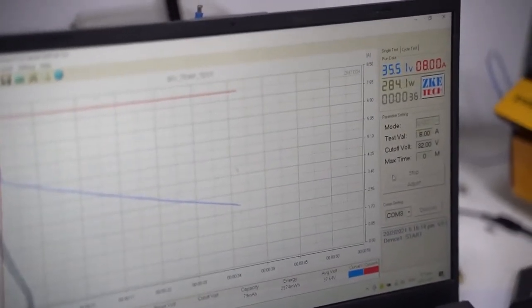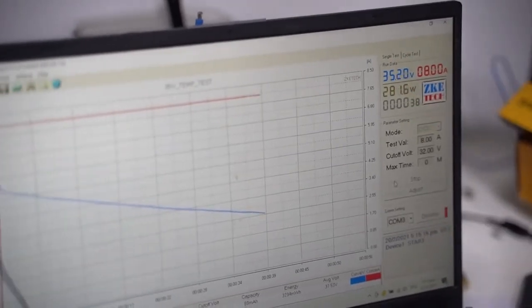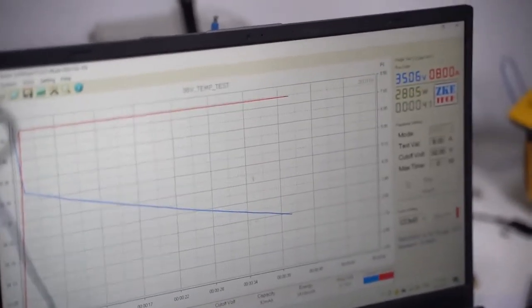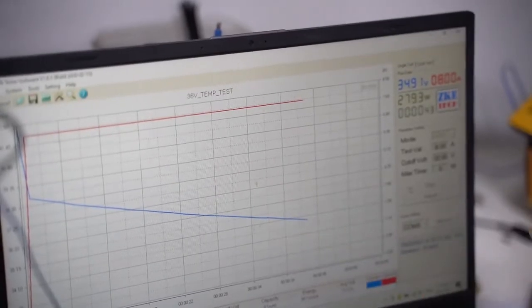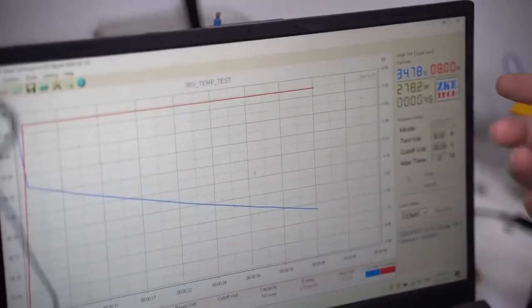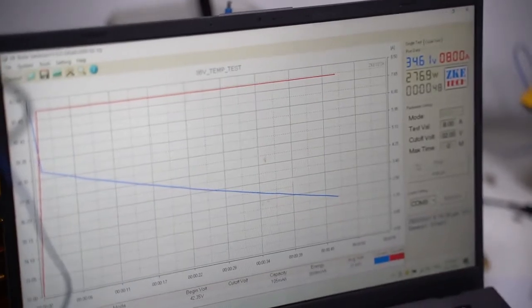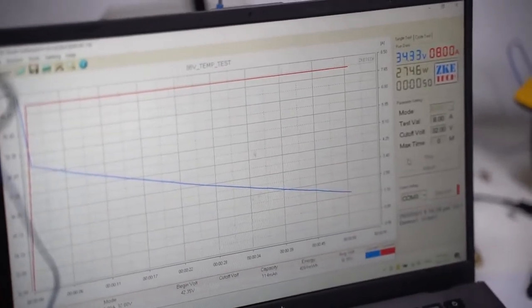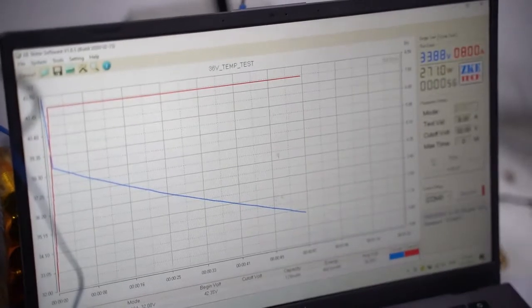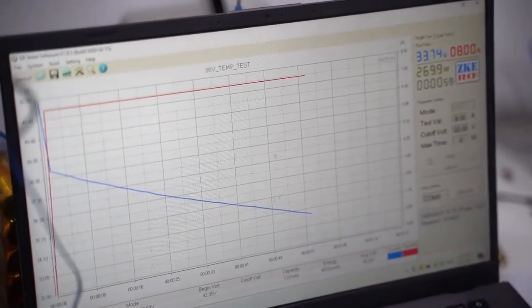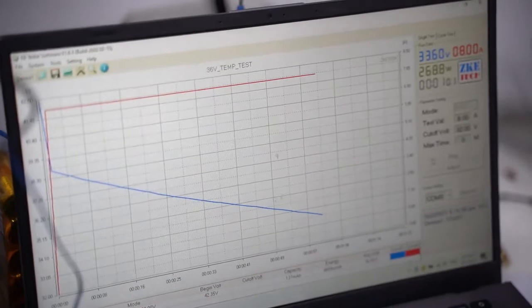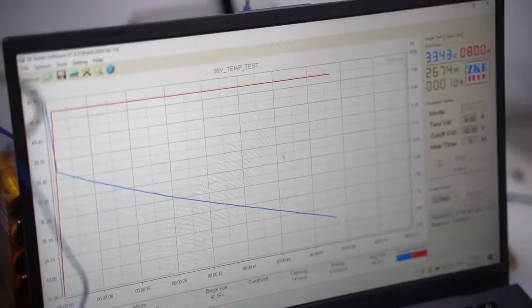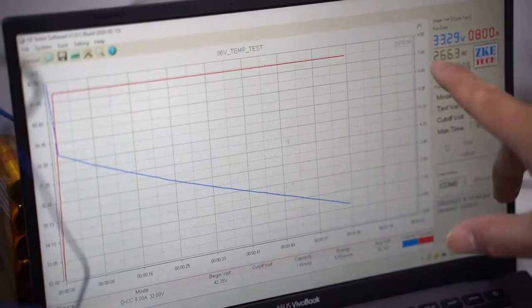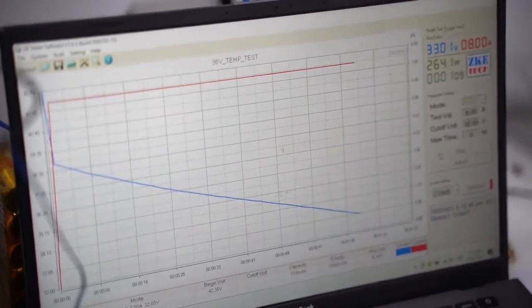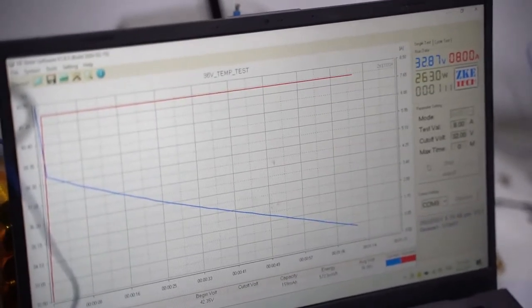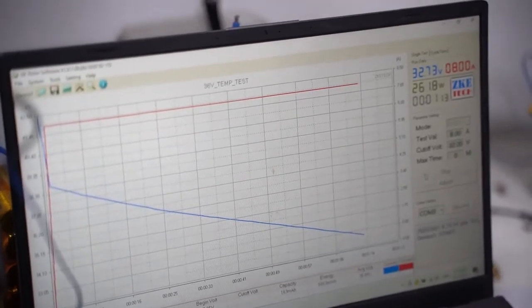It will cut off very soon because the cutoff voltage is about 32 volts. And at this rate you can tell that it's going to cut off within less than 5 minutes. Where previously, when we were running it in non-sub-zero conditions, it took at least 12 to 15 minutes to fully discharge to 32 volts. But given this rate, we're only 1 minute in, we're at 33 volts. It is going to be very fast before it hits that lower threshold.